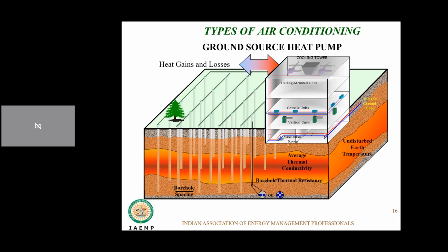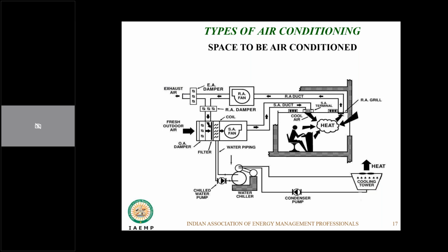Okay, so we'll now quickly understand how the space is air conditioned. We understood how the vapor compression system happens and how the heat transfer happens in the system. So let's say we have this evaporator coil. The air from the room, from the return duct, comes into the system. We'll talk a little more on the return air fan later on. It comes through the system, comes to an isolation damper in case you want the return air to come in or exhaust air to go out. You have this bypass damper.